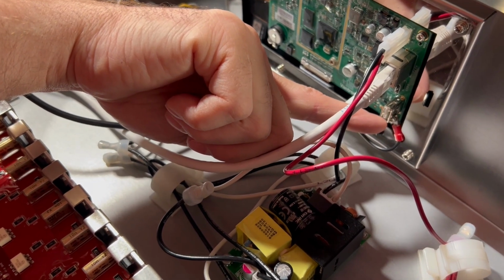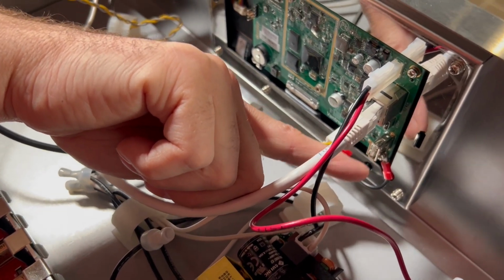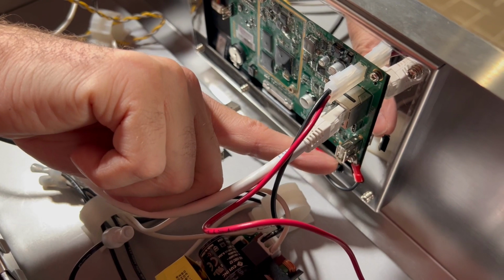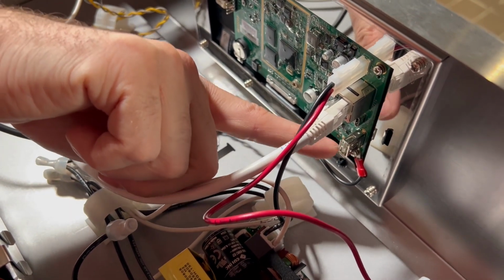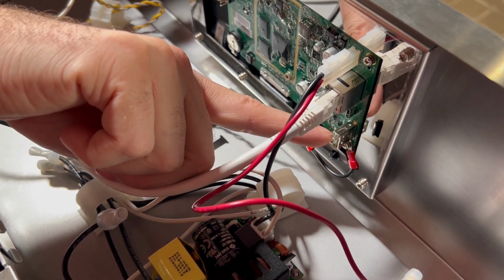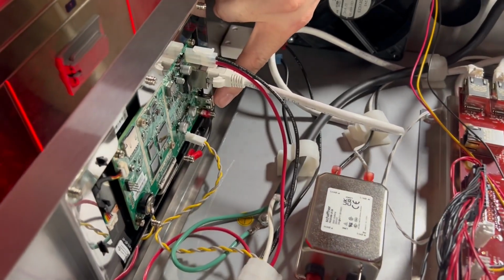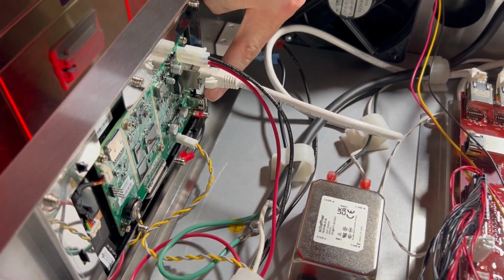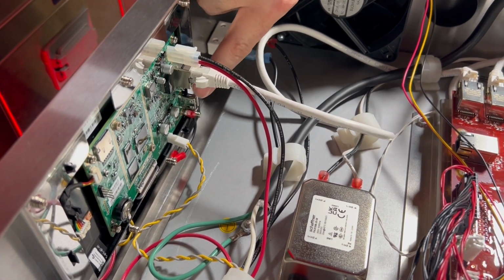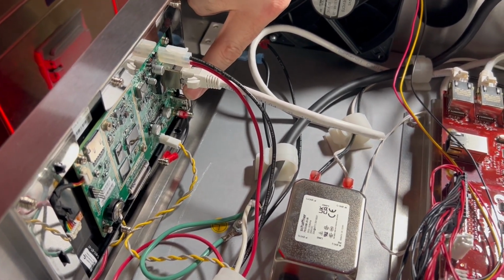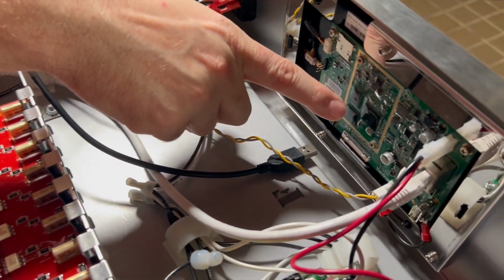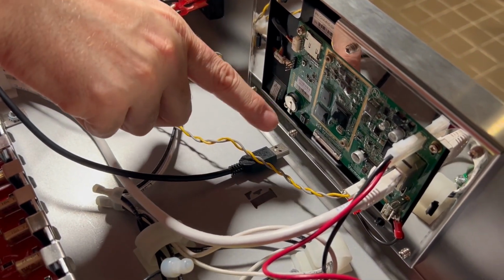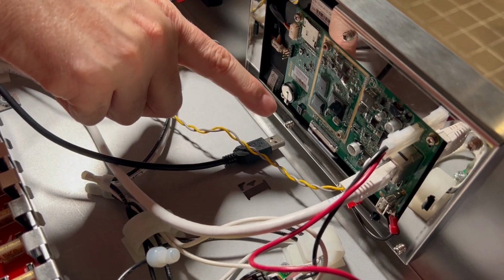Then we could try and see if that took care of the error code if we were either trying to import or export. If that still didn't take care of the issue, then we could jump to our back control and try the same thing on the USB port right here. So if it did work on this control but did not work on this front one, then we know we have an issue with this control, and we can proceed with potentially replacing it.